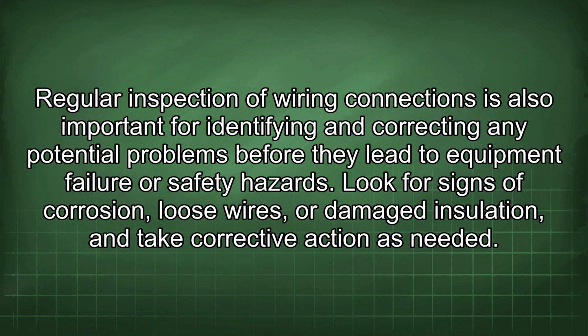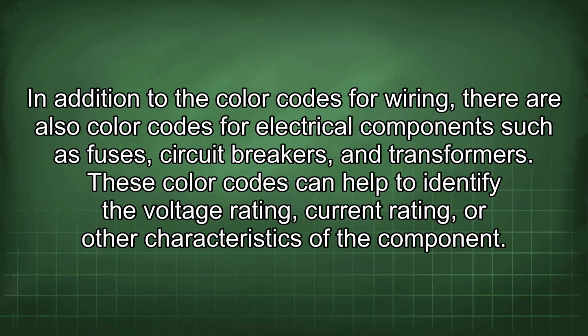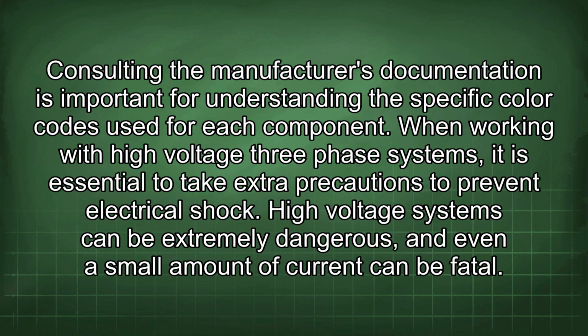Regular inspection of wiring connections is also important for identifying and correcting any potential problems before they lead to equipment failure or safety hazards. Look for signs of corrosion, loose wires, or damaged insulation, and take corrective action as needed. In addition to the color codes for wiring, there are also color codes for electrical components such as fuses, circuit breakers, and transformers. These color codes can help to identify the voltage rating, current rating, or other characteristics of the component. Consulting the manufacturer's documentation is important for understanding the specific color codes used for each component.